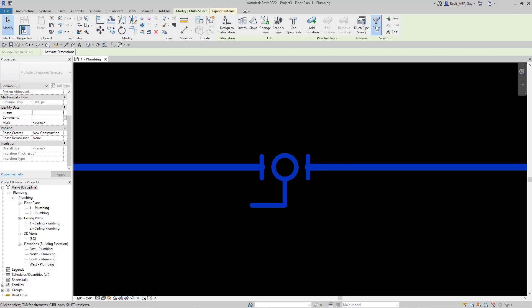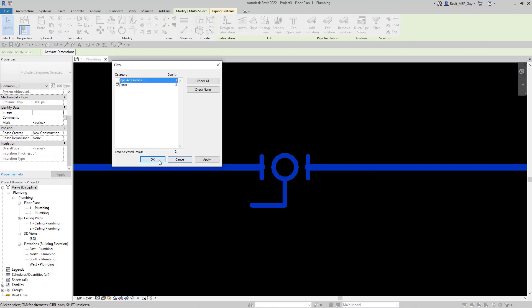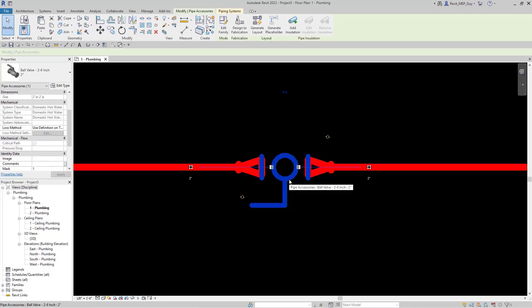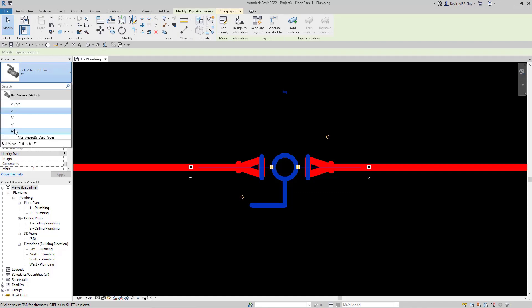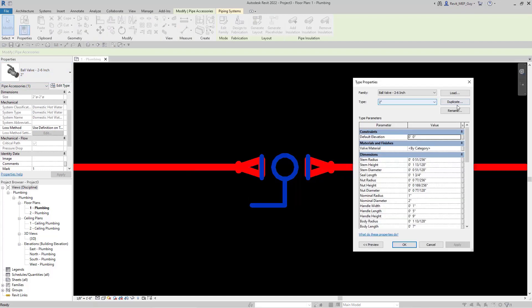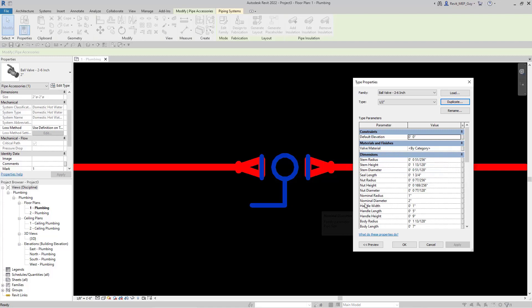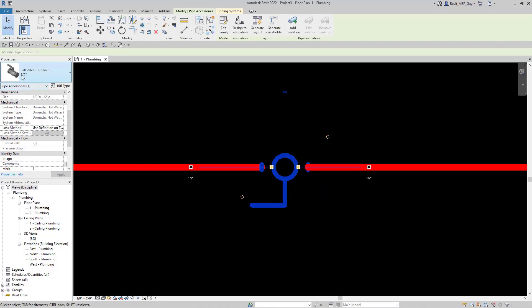I'm going to select everything, filter to deselect the pipe accessory, and Revit allows me to change the diameter to half inch — and you're going to see these increaser symbols. When we select our ball valve, we need to make it half inch, but there are no choices here, so we're going to have to create a half inch ball valve. I'll go to edit type, duplicate the two inch type, name it half inch, hit OK, change the nominal diameter parameter to half inch or 0.5 inches, hit OK, and now Revit updates to the half inch ball valve with no increaser symbols.